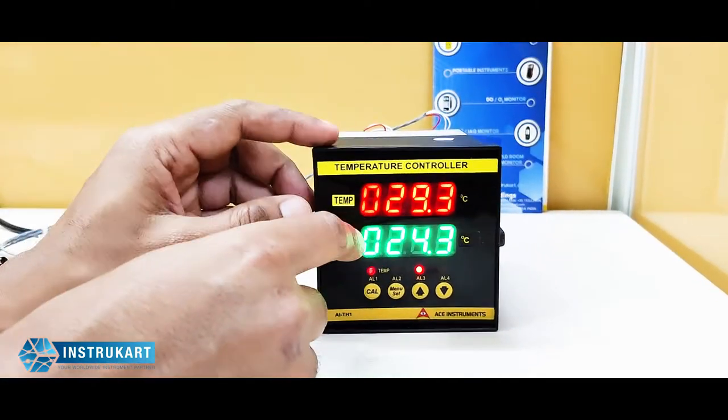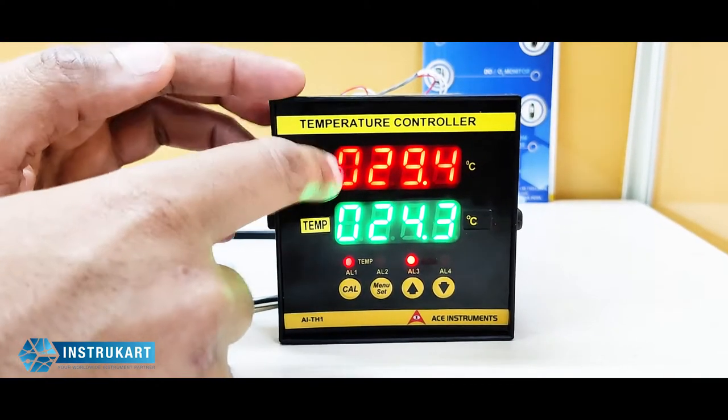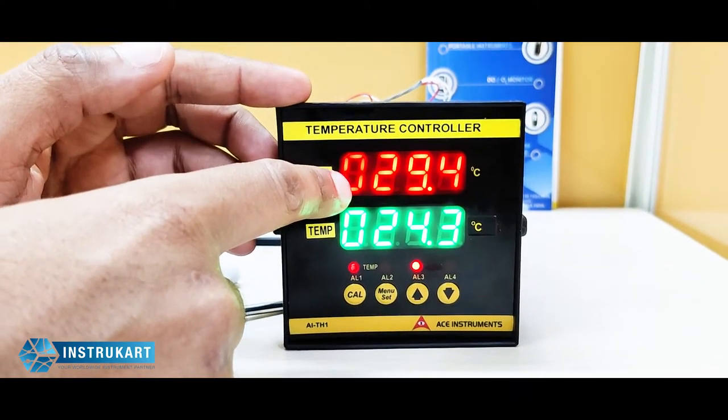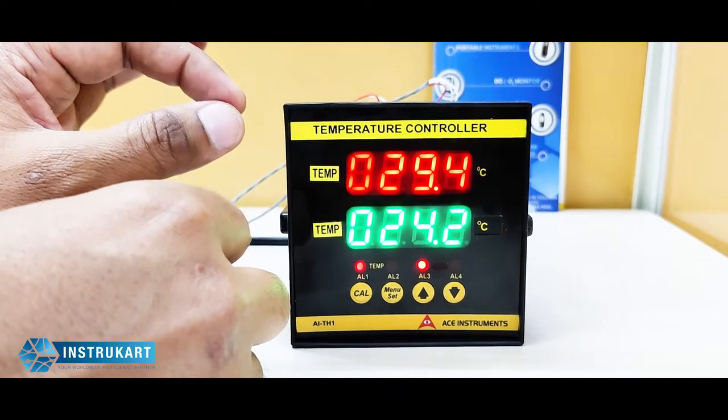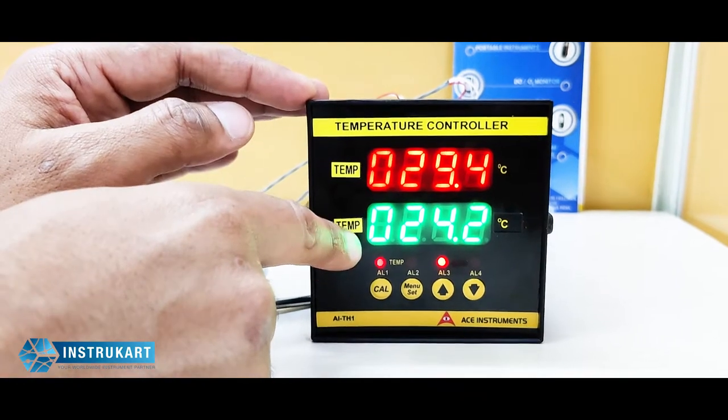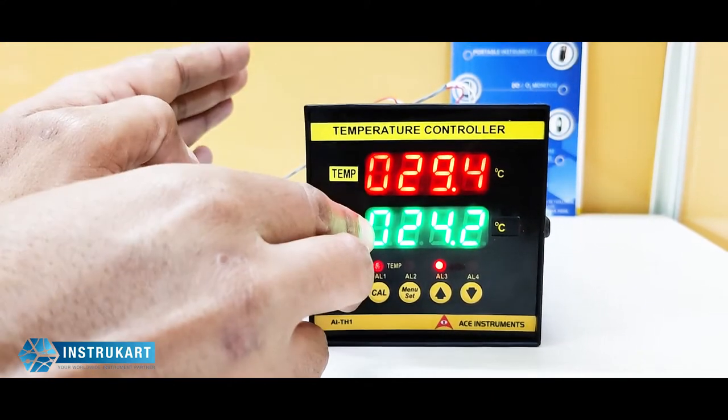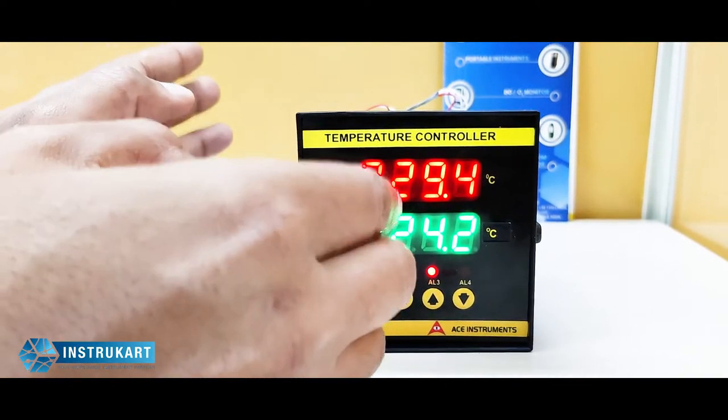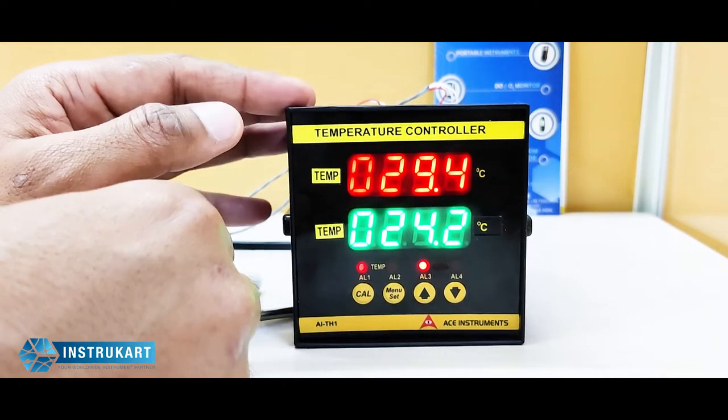Towards the controller, if we see, there are two displays as you can see, and these have also got two set points for each process value, which means low high for temperature 1 and low high for temperature 2. It has also got a relay option where you can control your motor, fan, or any pump based on the set point violation.